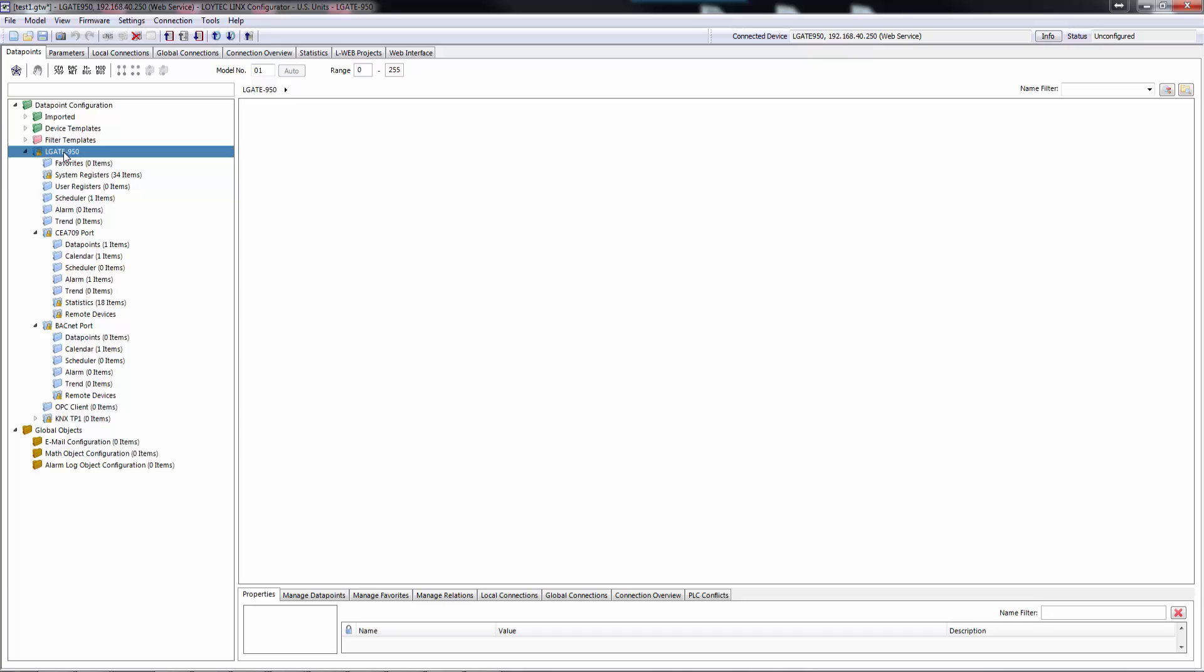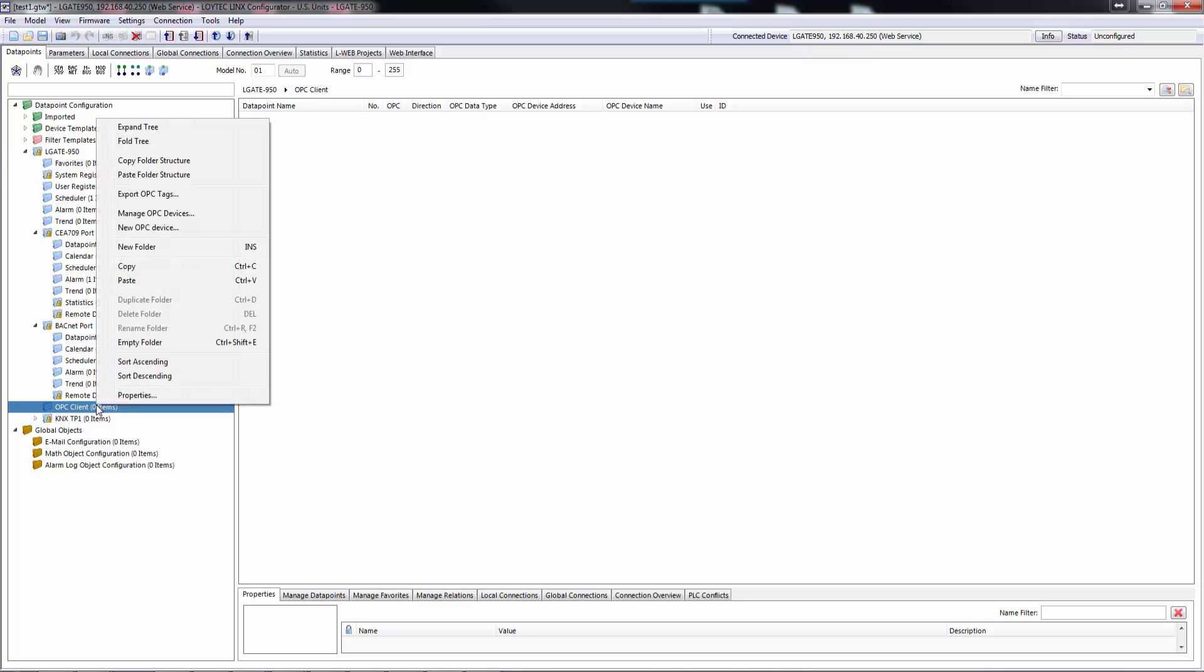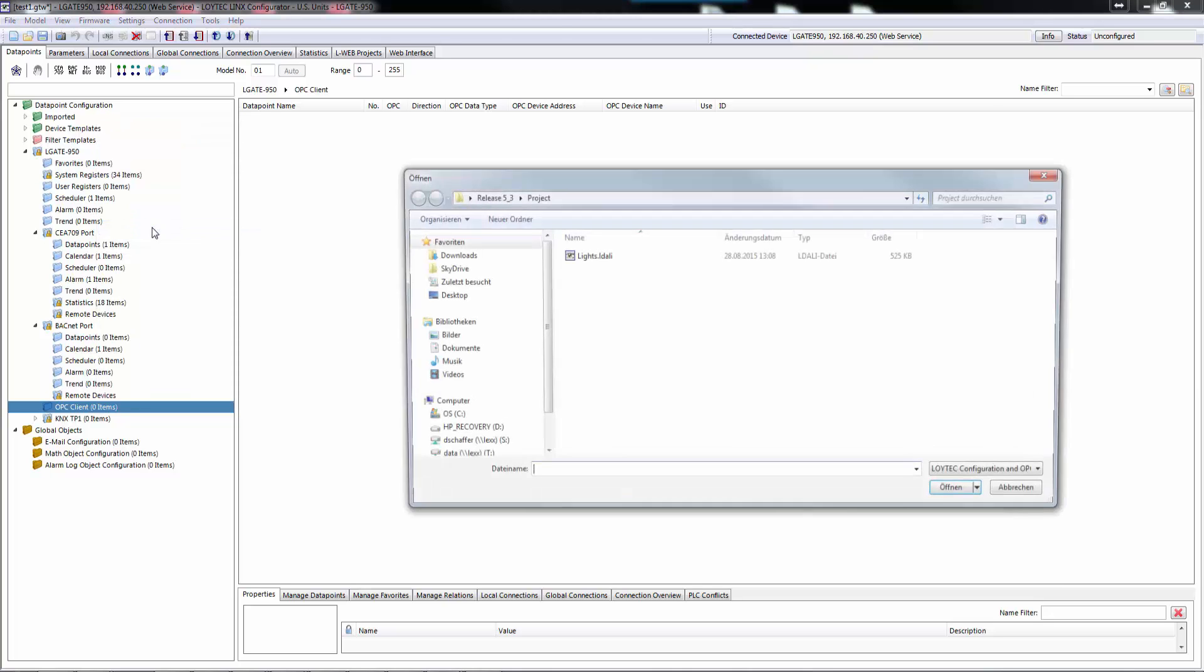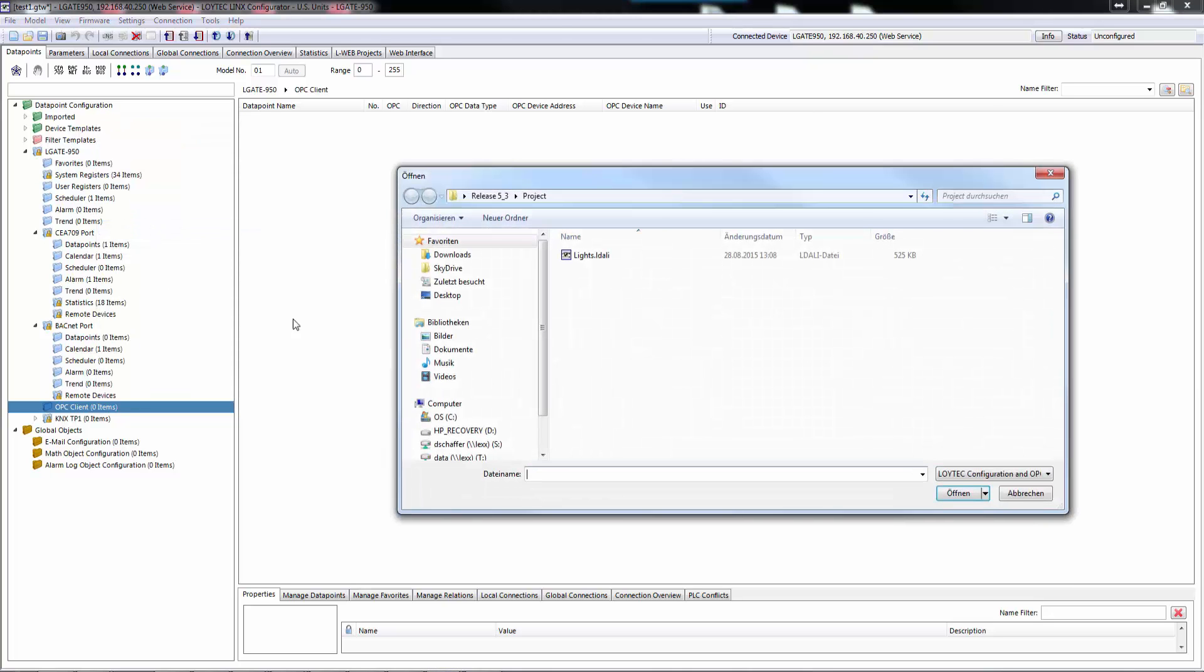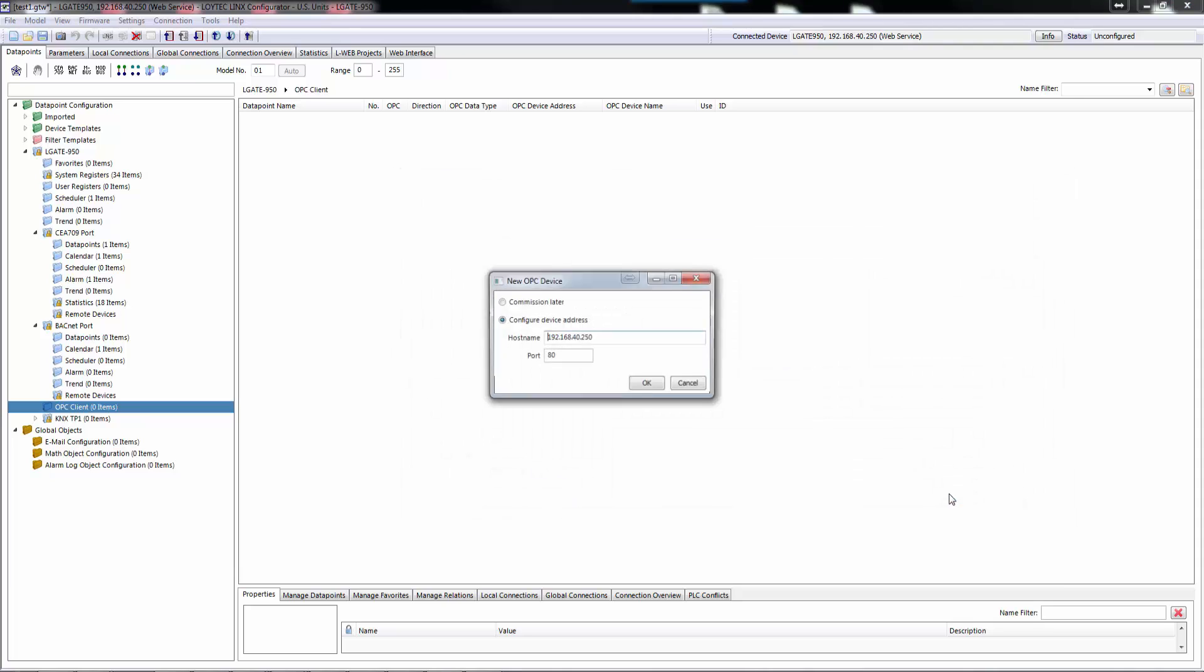To add an OPC server, select the OPC client port folder, right-click and choose New OPC device from the context menu. Select a LOYTEC device configuration file, such as a .links or .dali.